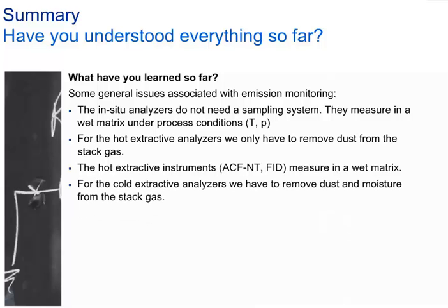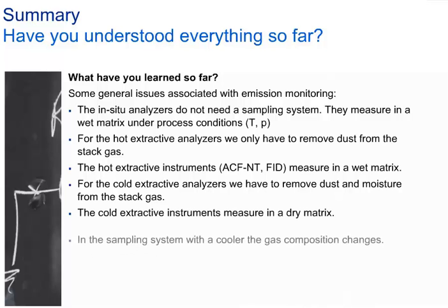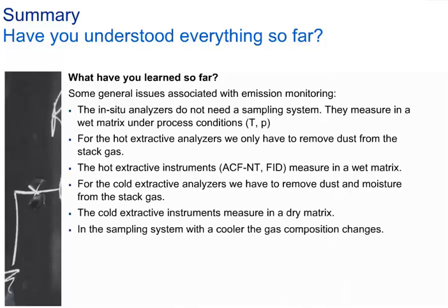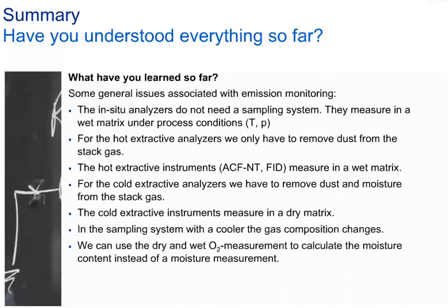For the cold extractive analyzers, we have to remove dust and moisture from the stack gas. The cold extractive instruments measure in a dry matrix. In the sampling system with a cooler, the gas composition changes. We can use the dry and wet O2 measurement to calculate the moisture content instead of a moisture measurement.